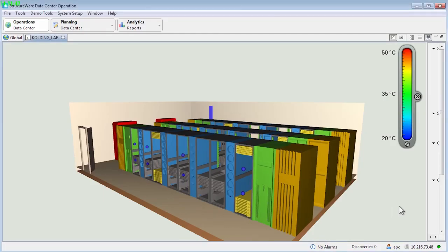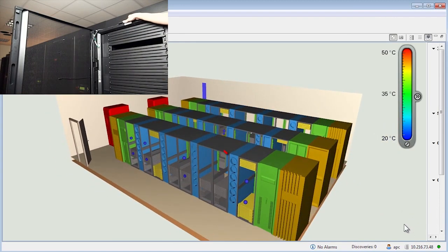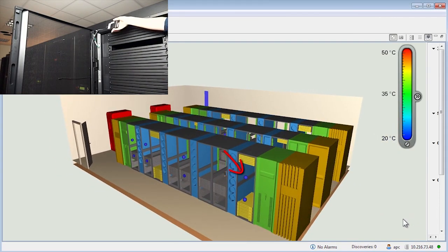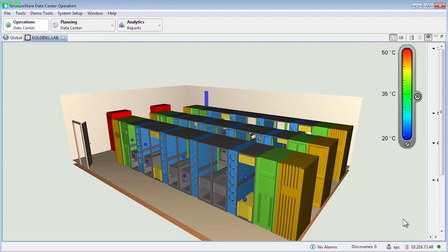At least every third rack should have temperature sensors. There are 2 sensors per rack, top and bottom. There is also a Cooling Optimize server, which could be placed in any rack.